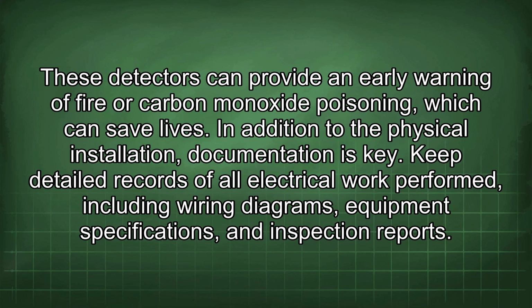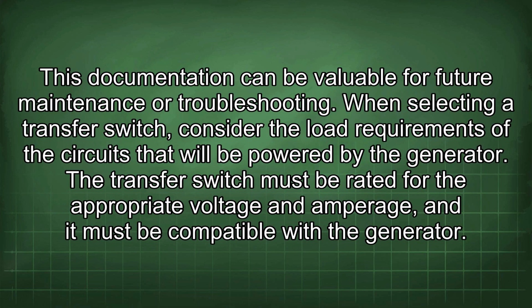In addition to the physical installation, documentation is key. Keep detailed records of all electrical work performed, including wiring diagrams, equipment specifications, and inspection reports. This documentation can be valuable for future maintenance or troubleshooting. When selecting a transfer switch, consider the load requirements of the circuits that will be powered by the generator. The transfer switch must be rated for the appropriate voltage and amperage, and it must be compatible with the generator.